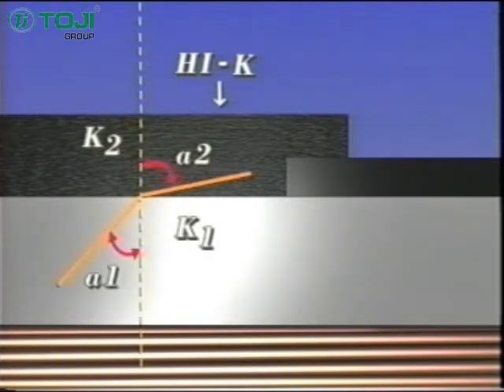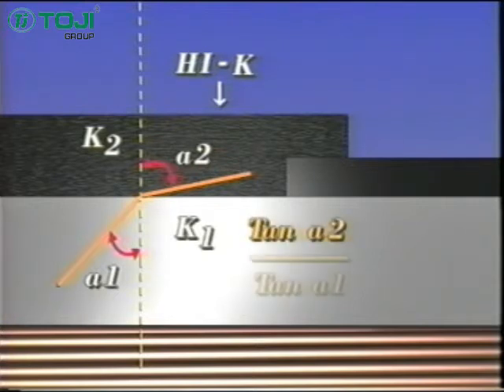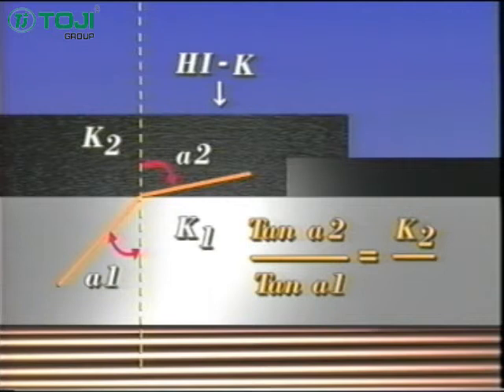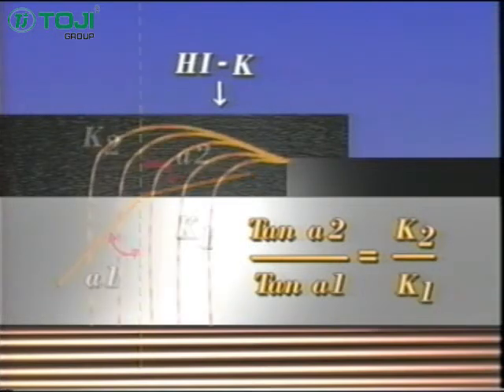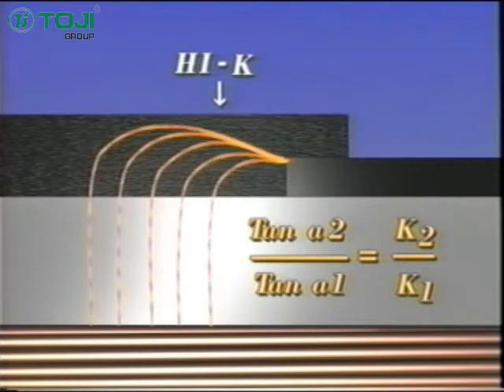The stress is reduced at the cable shield cutoff area by the principle of field refraction. A flux line, on entering an insulating material with a larger dielectric constant, will be refracted away from the normal line drawn through the interface. The degree of refraction is proportional to the ratio of dielectric constants of the two interfacing materials. The mathematical equation that governs the physics of the electrical field refractions is tangent angle 2 over tangent angle 1 equals K2 over K1. The refraction of the flux lines at the interface will result in a more uniform spread of the electrical stress at the cable end.